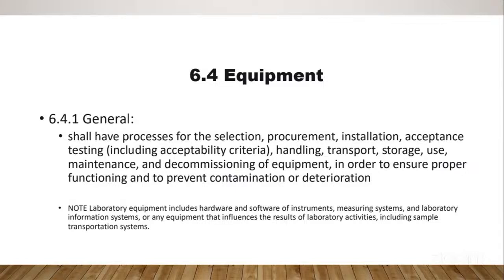When new equipment is brought into the lab, we should have an equipment installation data sheet where you register the name of the equipment, whether it's old or new, and the serial number of the equipment. There are four principal things that should be checked. One, where you are putting the equipment, whether it's exposed to direct sunlight, whether it's away from vibrations, and you check whether the equipment has a manual, and whether it even has a service manual. You will check all this, and in your equipment detail form, all these things will be ticked before we talk about the validation of the equipment.